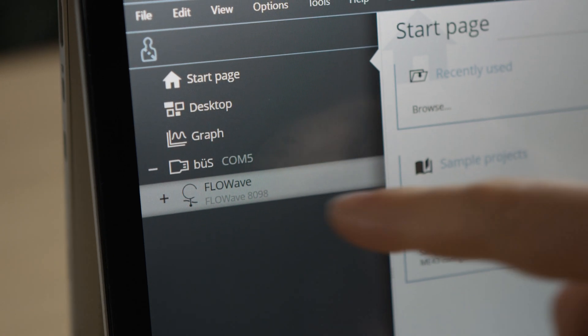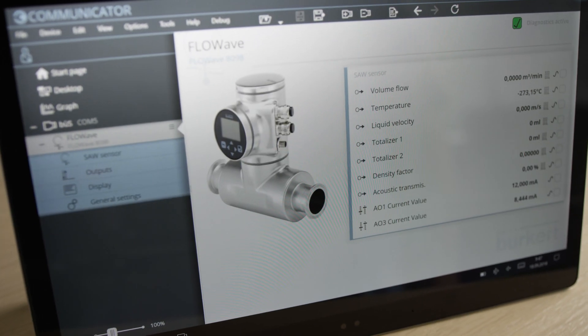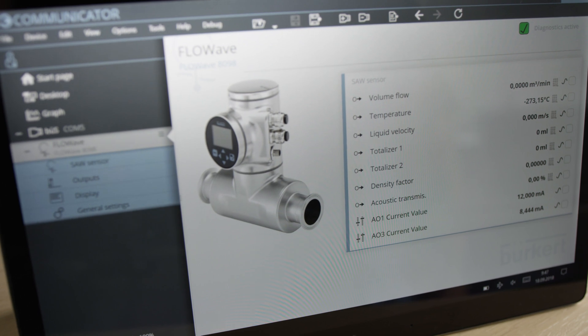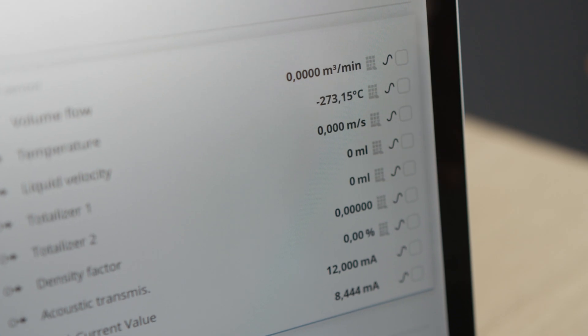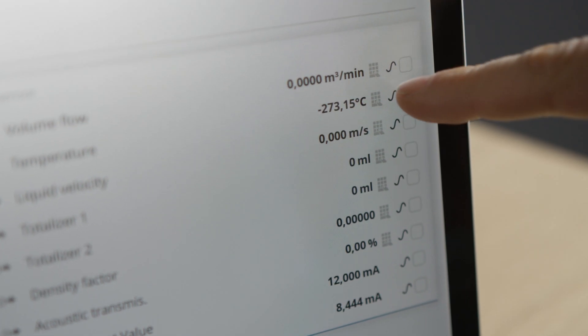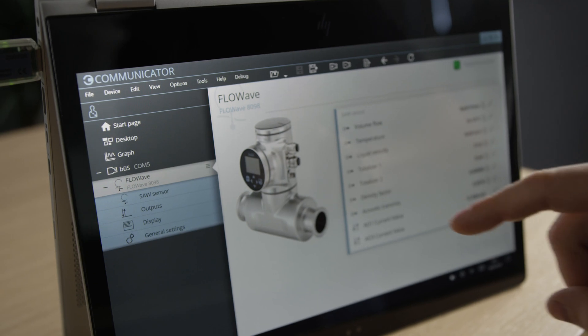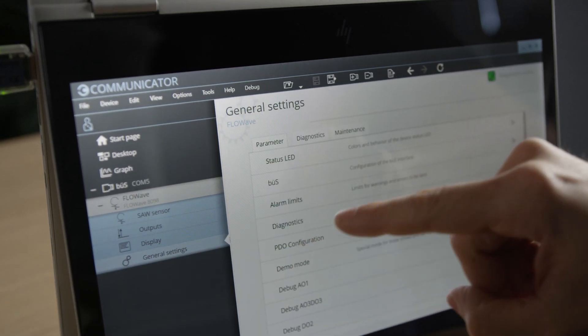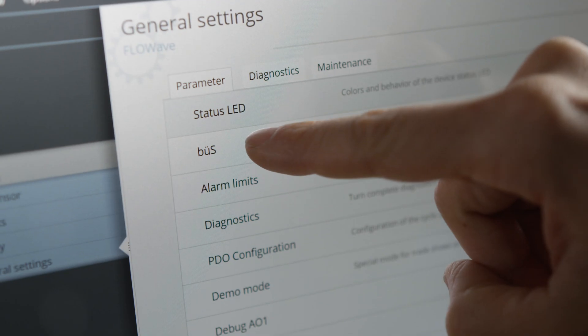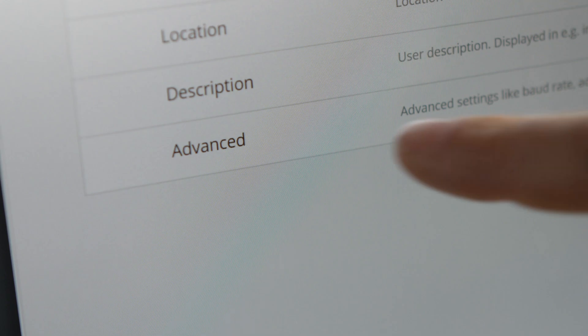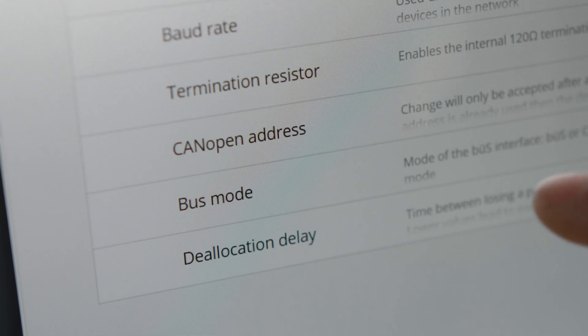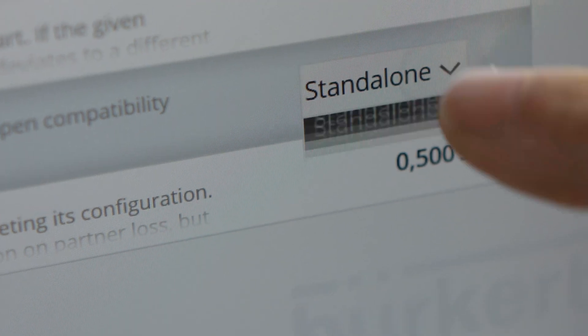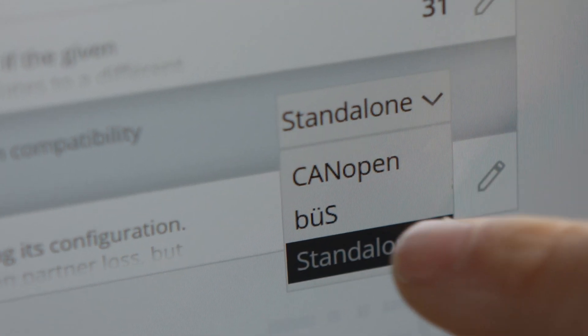FlowWave appears in the device list. To update measured values automatically in the communicator, you need to change the bus mode. To do so, select General Settings, Bus, Advanced in the menu and change Bus mode from Standalone to Bus.